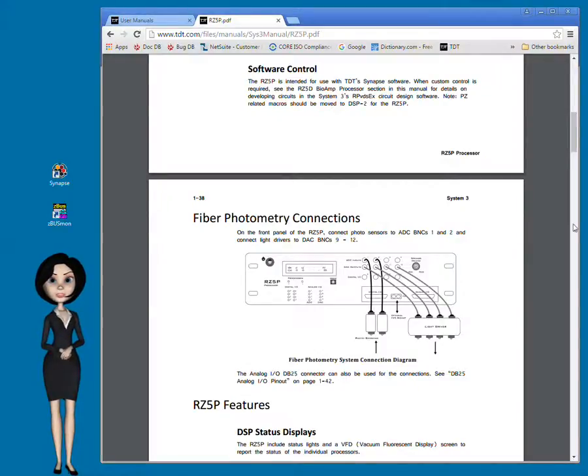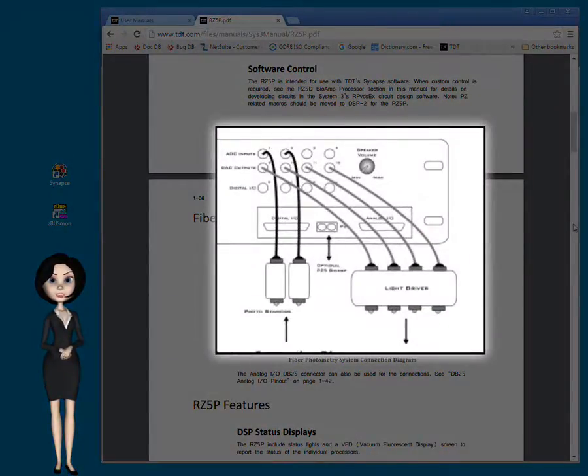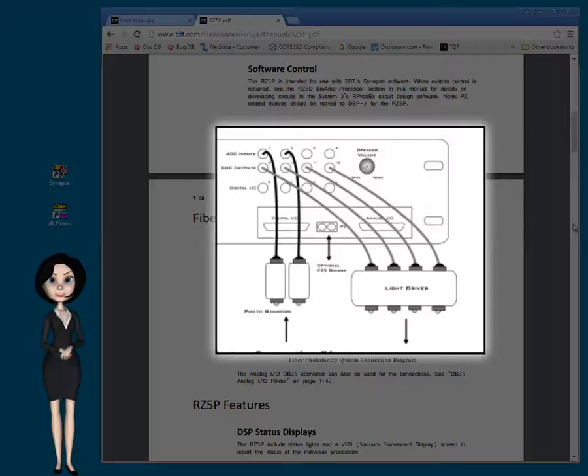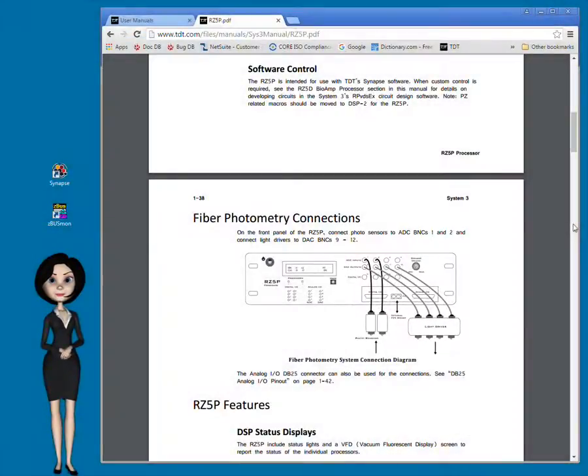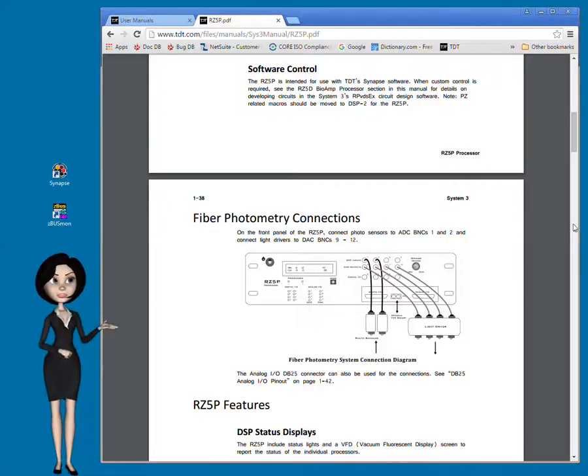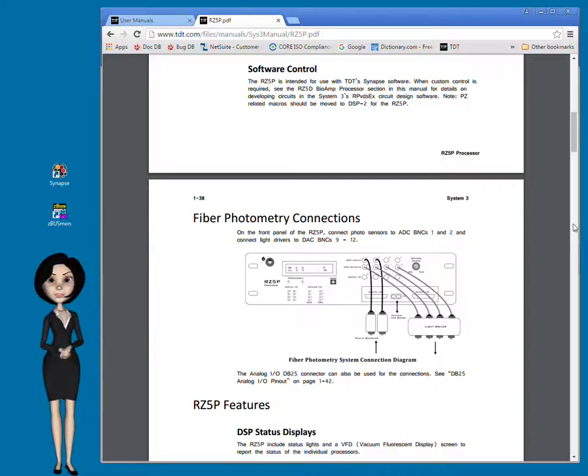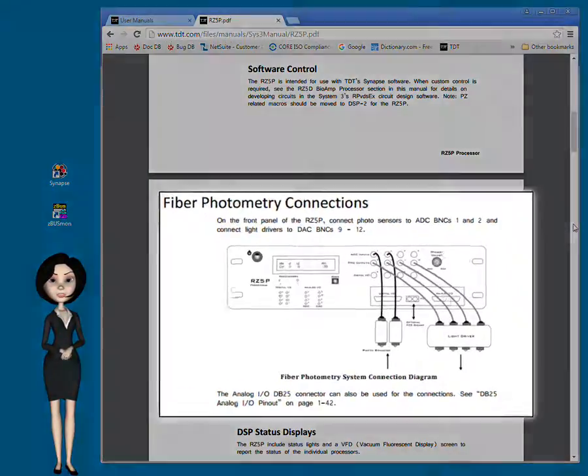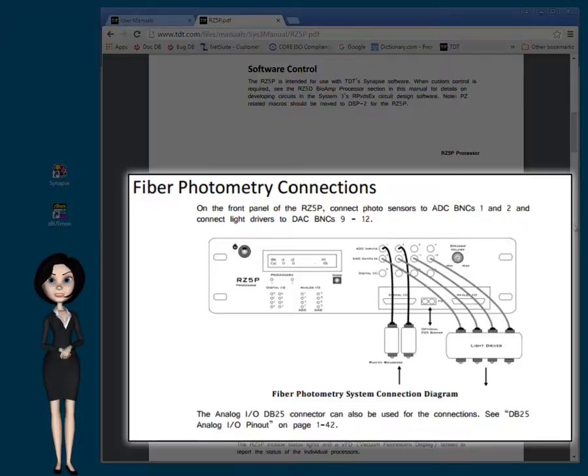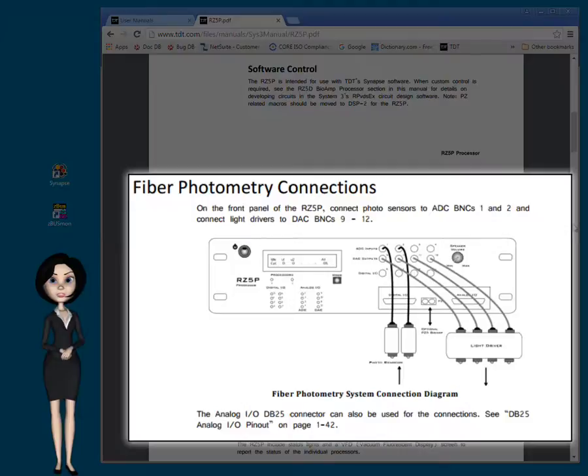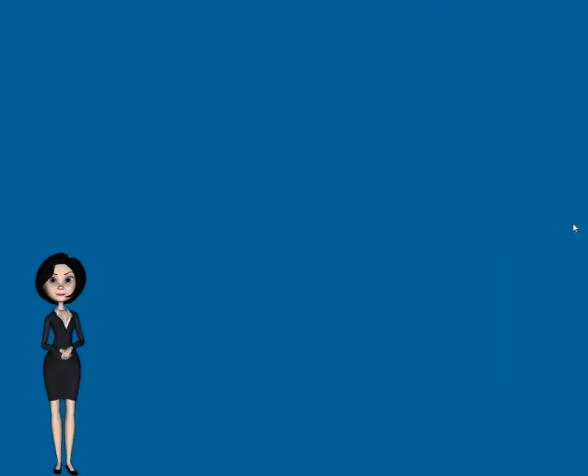To control the light drivers and record the sensor inputs, you'll use your device's digital-to-analog and analog-to-digital channels. Everything you need to run your fiber photometry protocol can be accessed using the BNC connectors on the front panel. Normally, you'll connect the sensors to the BNC inputs for channels 1 and 2, then connect the light drivers to the first 2 or 4 DAC channels. With the RZ5P, that's channels 9 through 12. With the hardware handled, let's move on to the Synapse software.